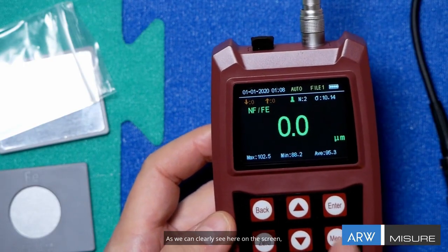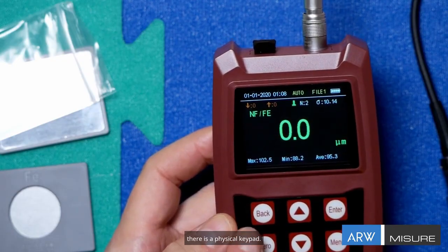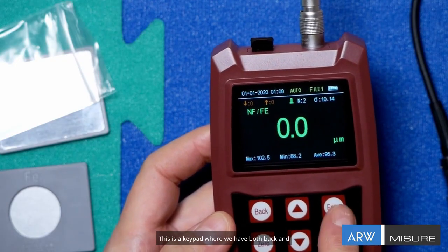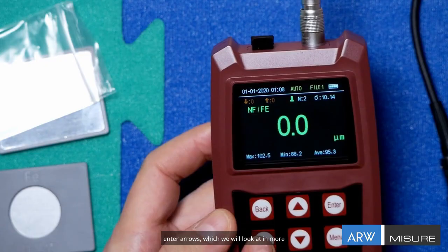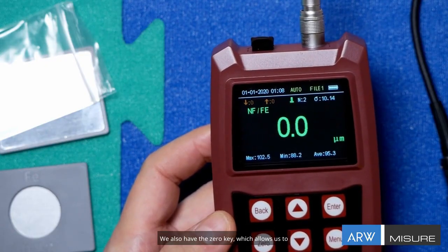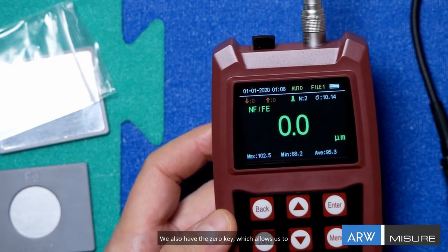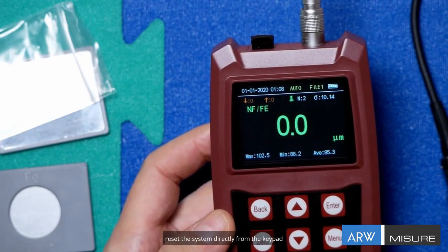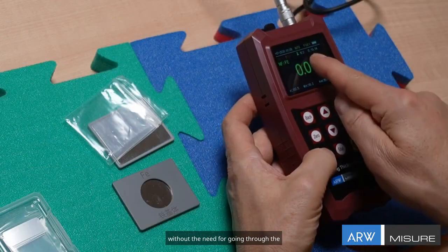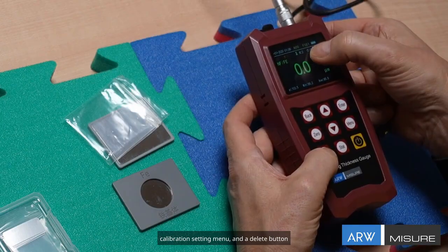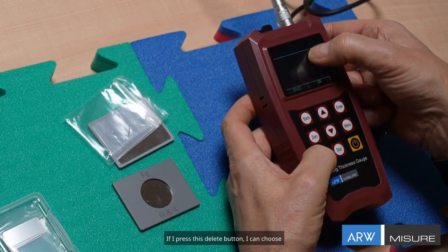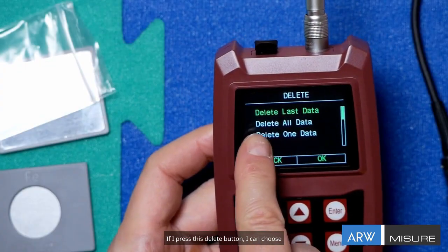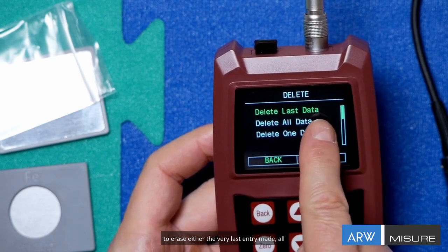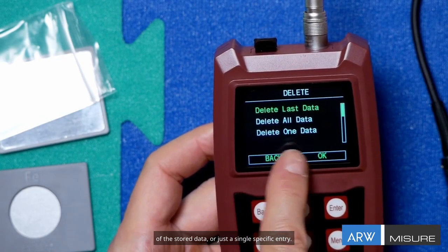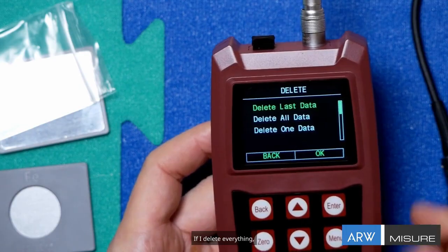As we can clearly see here on the screen, there is a physical keypad. This is a keypad where we have both back and enter arrows, which we will look at in more detail later on. We also have the 0 key, which allows us to reset the system directly from the keypad without the need for going through the calibration setting menu, and a delete button to erase our input. If I press this delete button, I can choose to erase either the very last entry made, all of the stored data, or just a single specific entry.